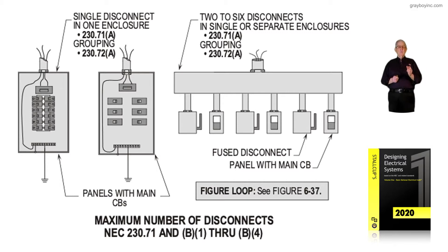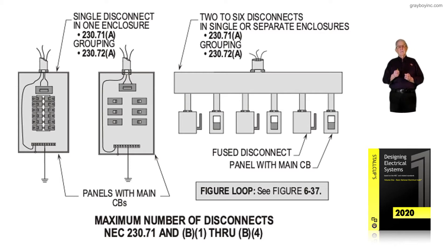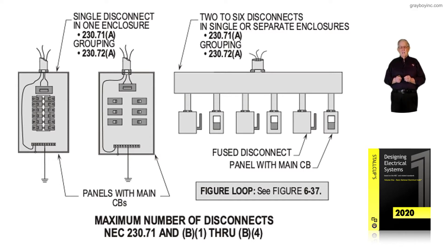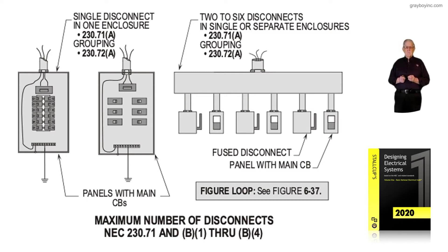To the left, we have a main ahead of those circuit breakers in that panel board, so everything is grouped in a single enclosure, but we had to have a main. In the 2017 edition and previous editions of the NEC, look at the service panel in the middle of the illustration. It has to have a main by the 2020 edition of the NEC. But the 2017 NEC edition, we could have had six individual mains in that panel board without a main ahead of them. Not so in the 2020 NEC.